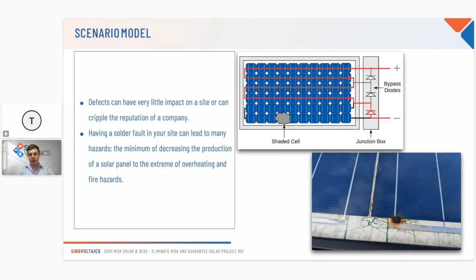As I said, you can have different scenarios caused by the solder fault itself. One, which is very common, is that the solder fault, like a shaded cell, will cut off the current from a specific block of cells, which activates a bypass diode, and you lose a third of the production from that module, which is no big deal by itself. But as these start to stack up, there is a bigger effect that can be caused.